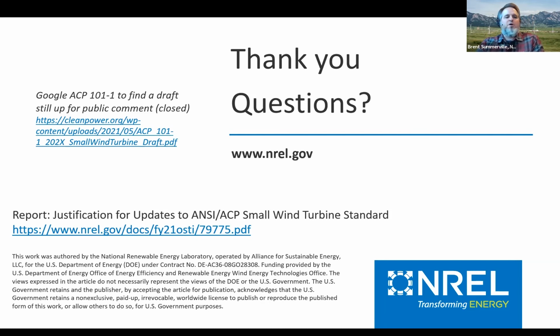And Mr. Kogan asks, how to establish the rated wind velocity as a result of rated power? The standard is standardized. So the large IEC 61400-12-1 has rated power at rated wind speed, which is not given, but this standard puts it at 11 meters per second. So what is the bin average power at 11 meters per second? That would be your reference power.